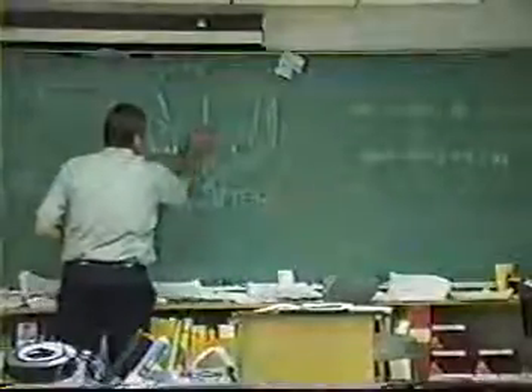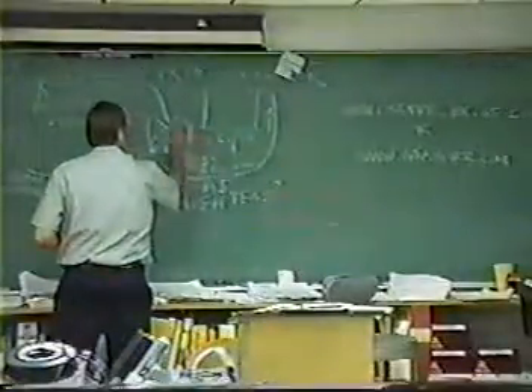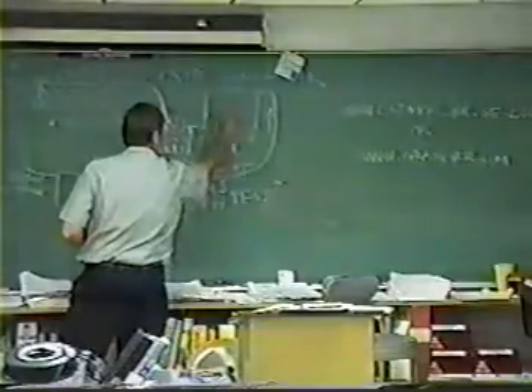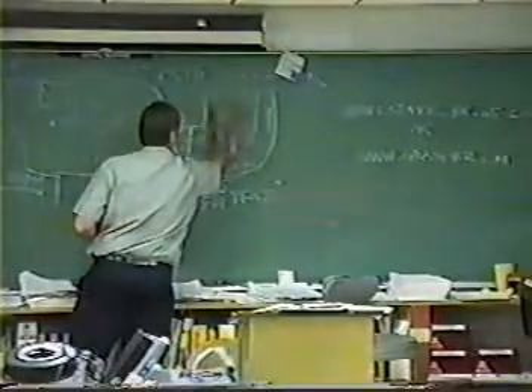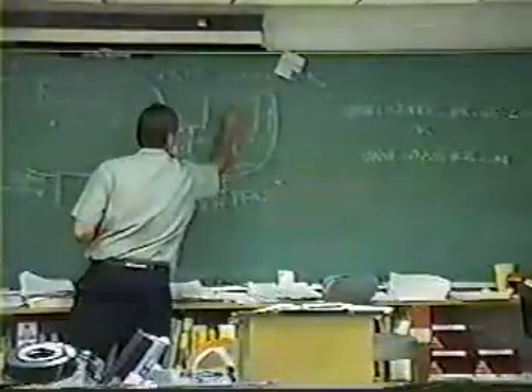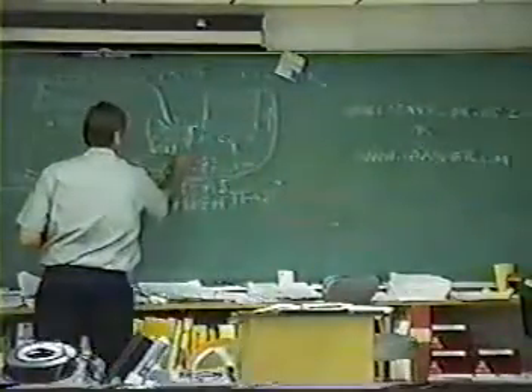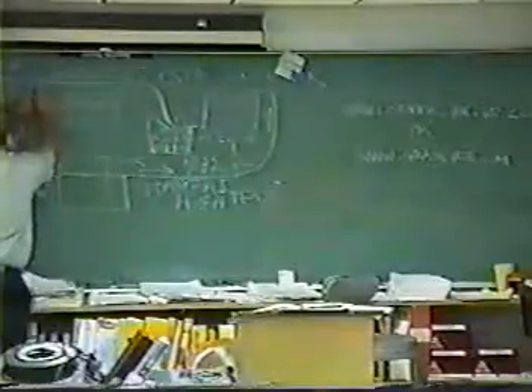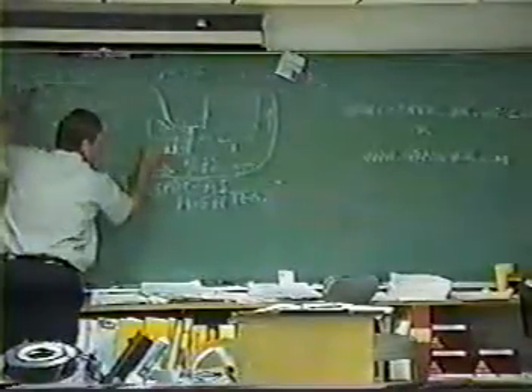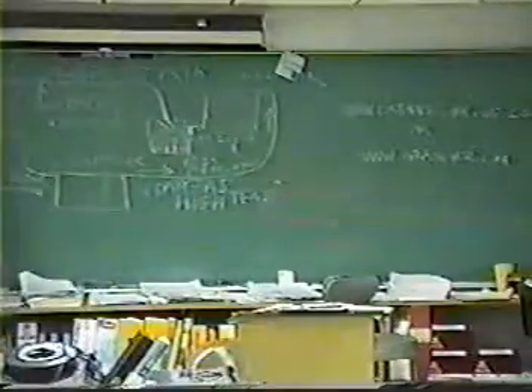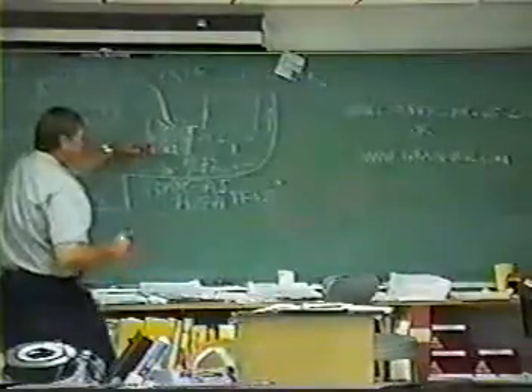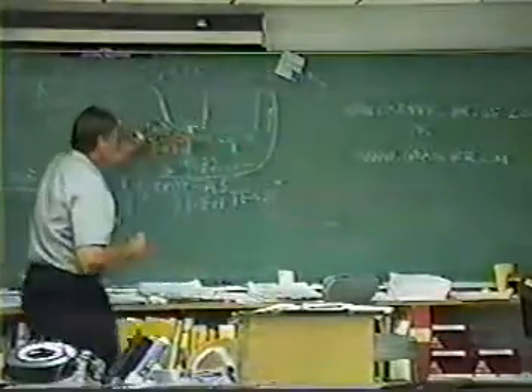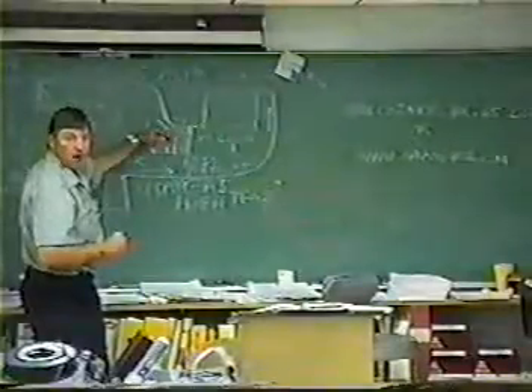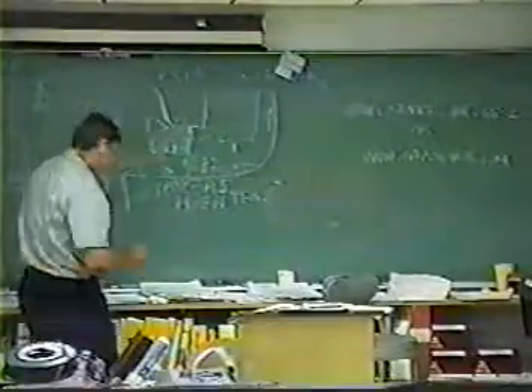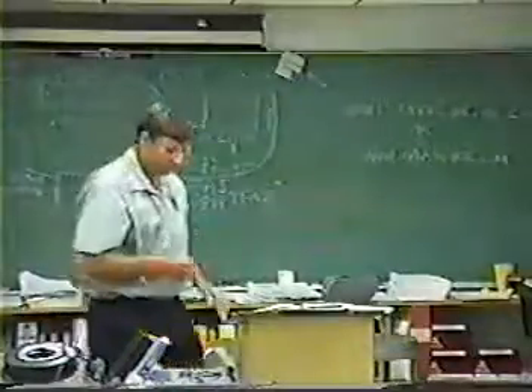Liquid receiver. We're leaving the condenser, coming in as a vapor at the top. We're condensing, going into your liquid receiver where you're storing it. The expansion valve, the level in your receiver will fluctuate according to the load on the evaporator. The freon comes in and out of here. It's actually stored in the bottom of your condenser, and it should be all liquid in that receiver. Every bit of it should be liquid in that receiver. Okay.